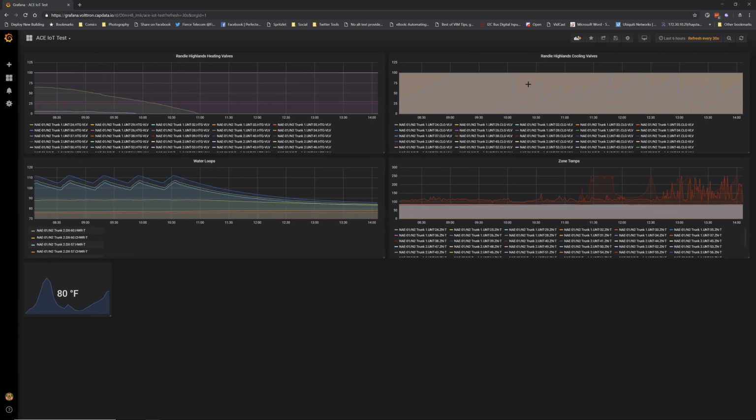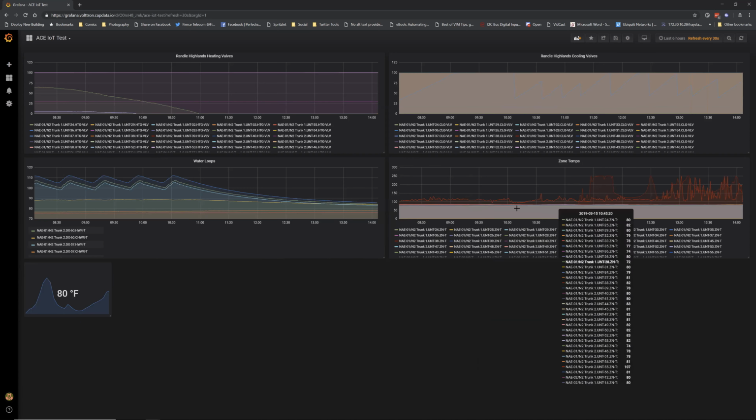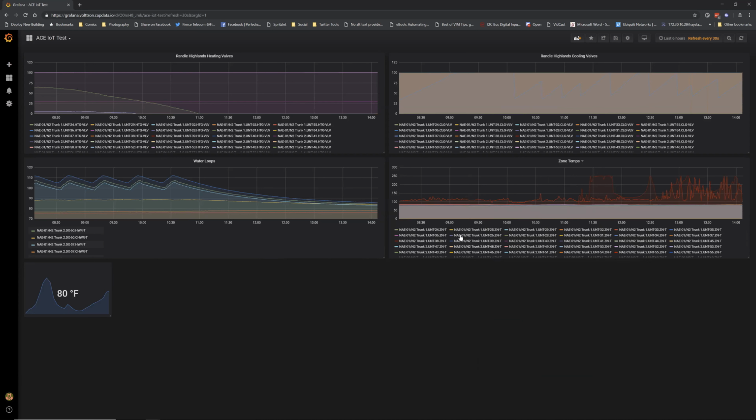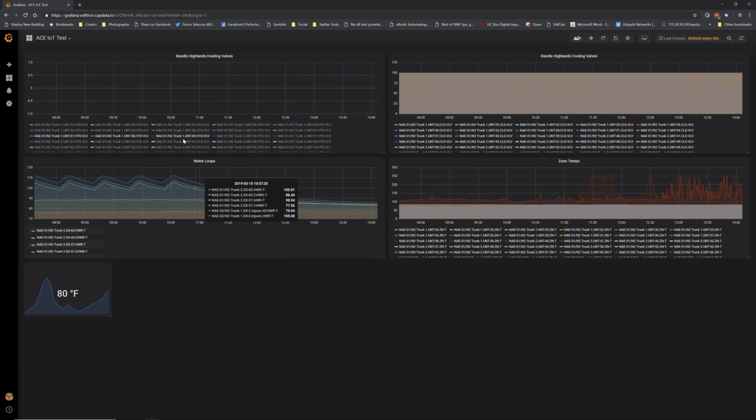So this is a very general HVAC use case of, hey, I want to know what's going on in my system. I've got a customer calling me and they're saying that this particular space is not within spec, and I want to know what's actually going on there, what's going on with the equipment that's feeding that. And off the bat, you get the ability to isolate particular data points like this. So I just want to see those 3 values. Well, all those valves are completely closed. That's not very interesting.